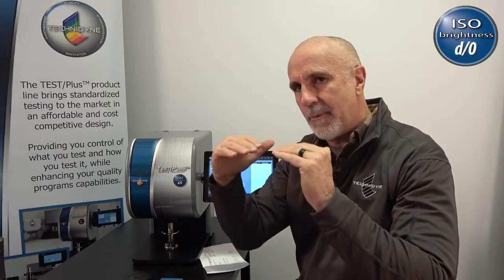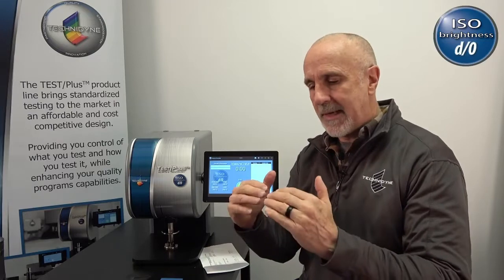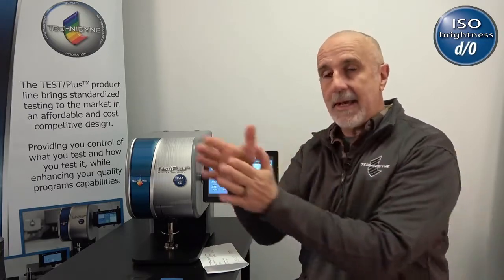So whether you're doing the primary calibration or the quick calibration, your goal is to bring that instrument back to that stable point. And that's very critical if you're making optical measurements, that you're able to maintain your calibration point from yesterday to today to tomorrow.